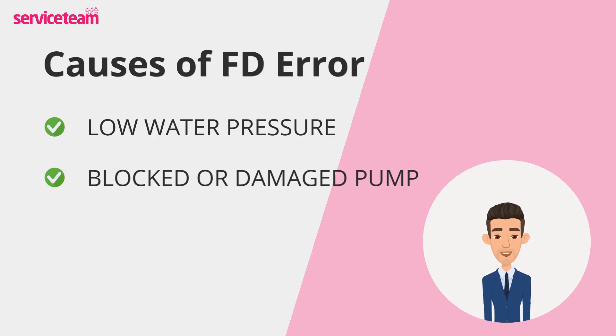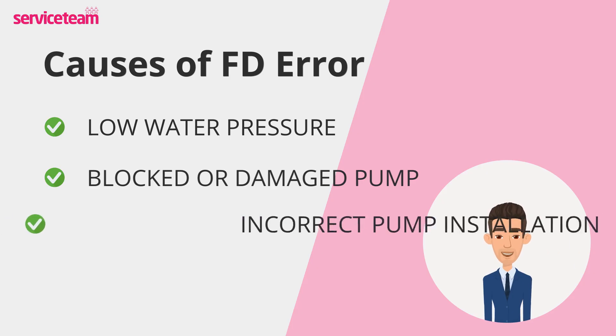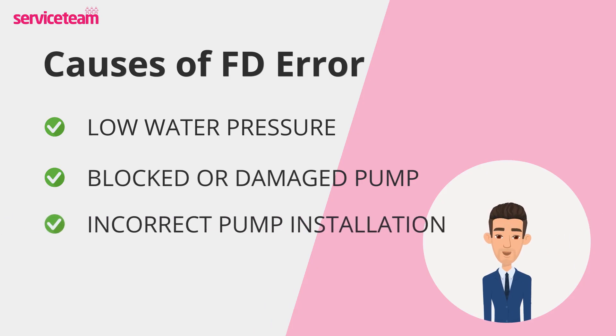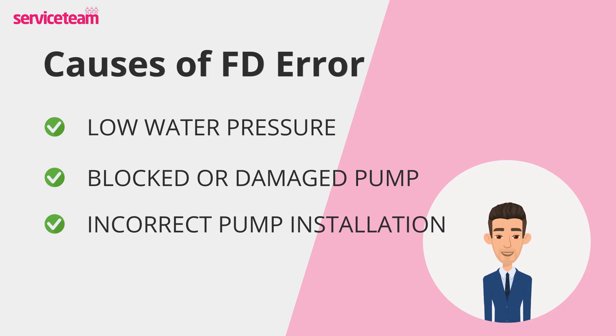This issue may be caused by heating sludge buildup or wear and tear on the pump's shaft or bearings over time. Another cause is incorrect pump installation. If the pump wasn't set up correctly — if it's not properly aligned or fitted — it can impact water flow and trigger the FD code too.